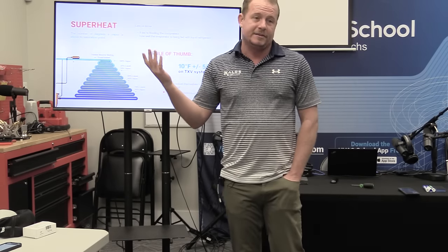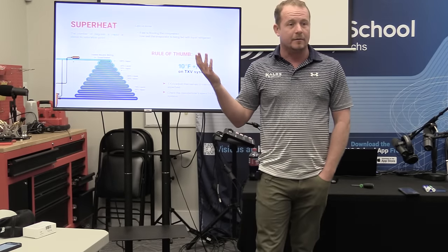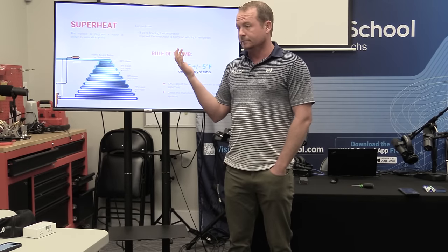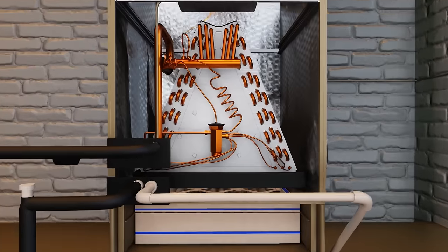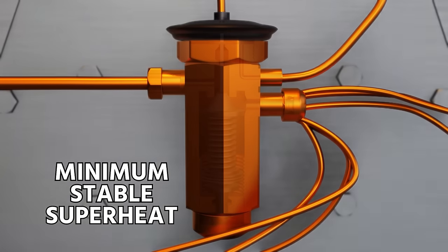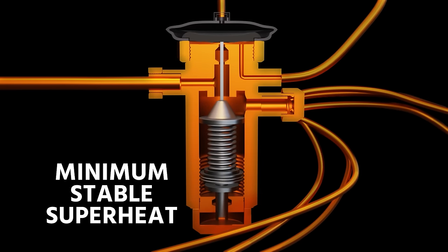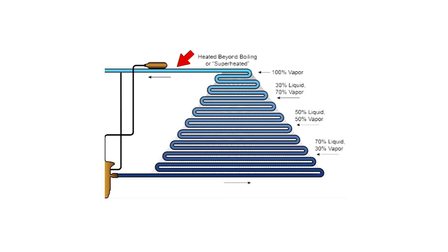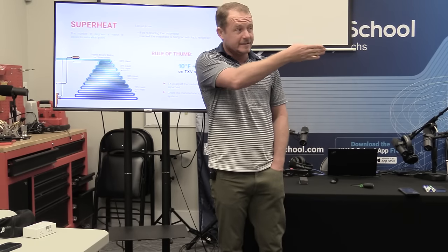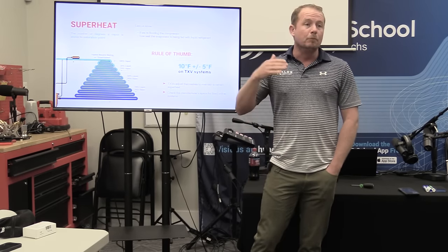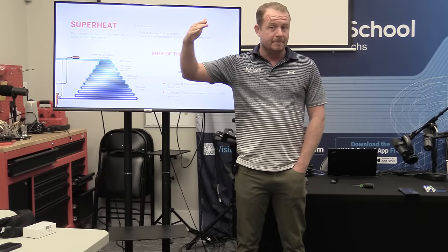Then the question is: why don't we just get superheat as low as possible — why not get it to one degree? We could get liquid back to the compressor. Because the metering device, in this case a TXV, has a minimum stable superheat. In order for it to balance out, it has to have a little buffer. So these are set so that in residential we most commonly see at the outlet of the evaporator coil something around 12, 13, 14 degrees. But sometimes tighter — I've seen units that run more like 6 or 7.